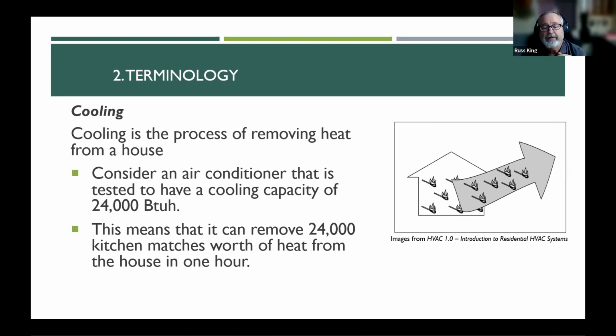So consider an air conditioner that is tested to have a cooling capacity of 24,000 BTUH, BTUs per hour. That means it can remove 24,000 kitchen matches' worth of heat from the house in 1 hour. Now, will that cool the house? Well, it depends on the load. You have to do a load calculation to determine if that's going to work. If your load calculation comes out at 23,000, then 24,000 is good. That's a little bit more, which is what you want. If your load calculation comes out at 28,000, then your 24,000 is not going to keep up, and the heat is going to come in faster than it's leaving.